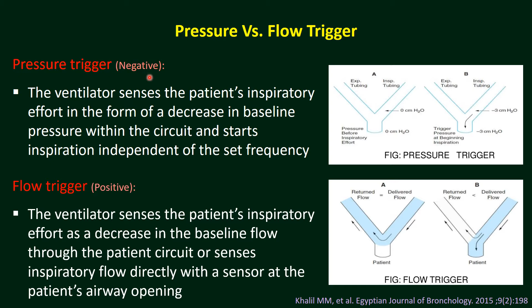So, in your ventilator you will find pressure trigger or flow trigger, both may be present, or in older versions of ventilators flow trigger may not be present, you will find only pressure trigger. Pressure trigger you will find as negative, like minus 0.5, minus 1, minus 2, etc., and flow trigger is positive.